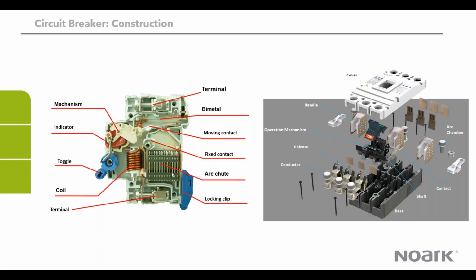Then we have the bimetallic part, which takes care of the overload situation. Basically, it's two metals that have two different linear expansivity coefficients, so they expand at different rates. When the circuit starts experiencing overload, it's going to heat up. But because the two metals touching each other don't have the same linear expansivity, one is going to expand faster than the other, so it's going to make a kind of arc or curvature. That expansion is what causes the trip mechanism on the breaker to be triggered, and then you're going to have a trip.